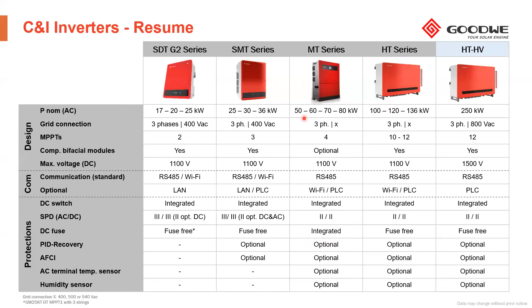Regarding the MPP trackers and the strings, it's good to mention that most of our portfolio is fuse free. That means we design and build our inverters with two inputs per MPP tracker, so we don't need to protect the string or the MPP tracker by fuse. In the 25 kilowatt model, there are 3 inputs in the first MPP tracker, so that would require external protection. But in general, it's fuse free, or in the case it's not, it's already integrated.